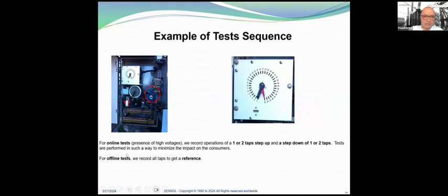Example of tests sequence for online test, in the presence of course of high voltage. We record operation of 1 or 2 taps, step up and step down of 1 or 2 taps, and tests are performed in such a way as to minimize the impact on the consumers. Of course, as soon as you work online on your transformer, your consumer will not be happy. For offline test, we record all taps to get a reference.